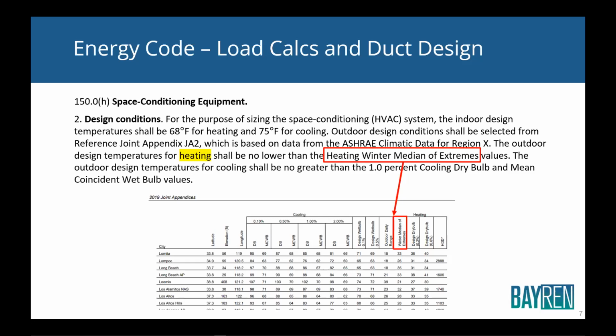And that means that by definition, it is actually hotter than that temperature 1% of the time. And that's not very much, but you would look at that temperature and say, you know, you're designing to 95 and we hit 100 last week. Why are we designing to such a low temperature? And if you look at the graph of outdoor temperature, it rises up, it peaks, and it drops down. And so it's only at that really hot temperature for a very, very short period of time.